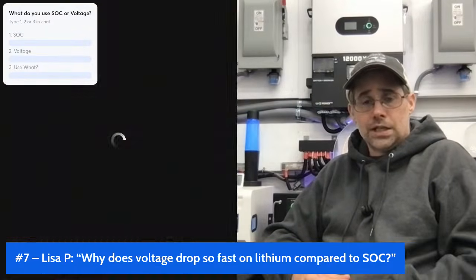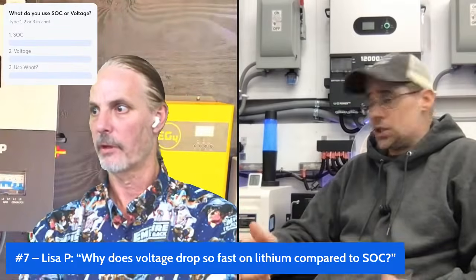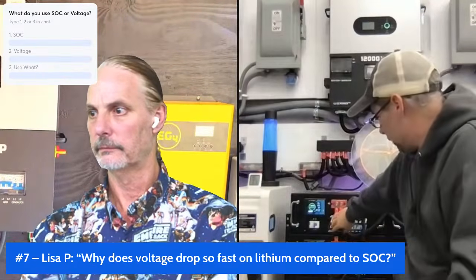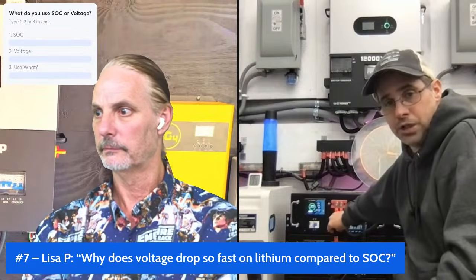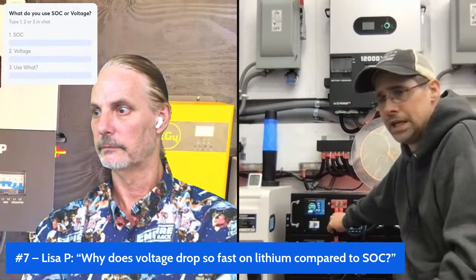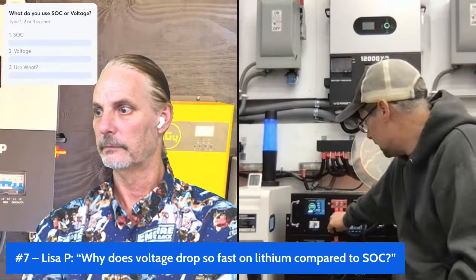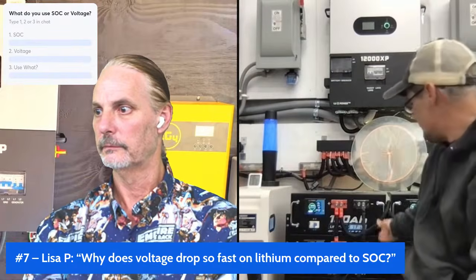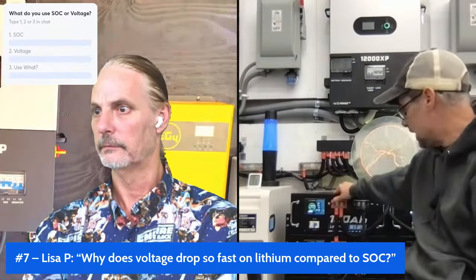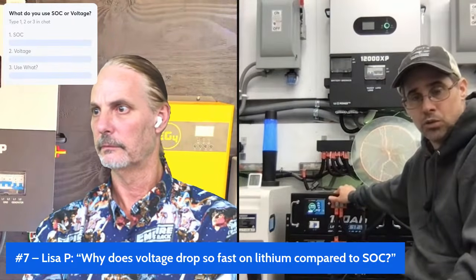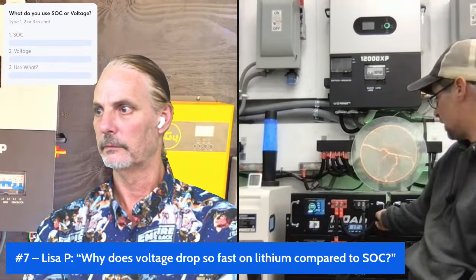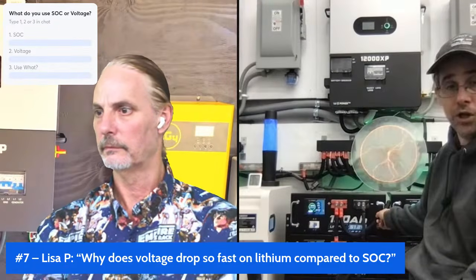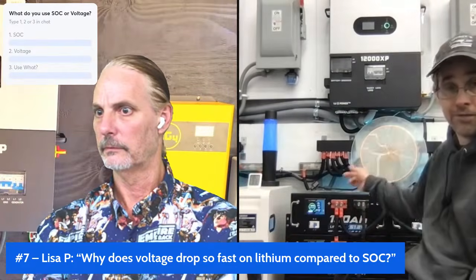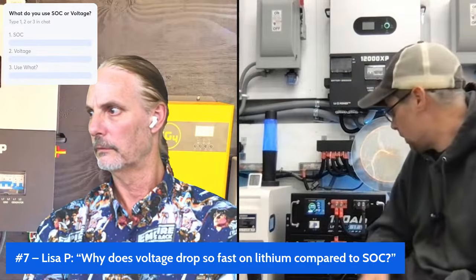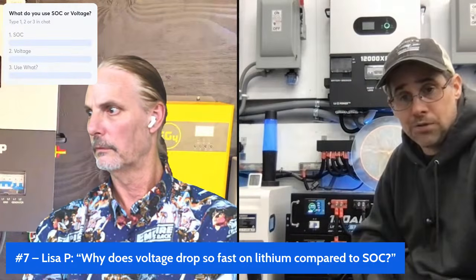Definitely overdo the wire size for the amount of amps that are going through. I've got 2/0 cable, and a lot of these batteries come with very thin cable to connect them all together. Some will use 4 gauge, 6 gauge. 2 isn't bad. But the problem is, if I take the output of these 3 batteries that are connected together, each one has a 100 amp BMS. Well, that's 300 amps that can go through this wire, and I've got 2/0, so I can flow a lot through it. And then I have it fused for that 2/0 cable. But you don't want to go with thin cables, because it's going to be very hard to keep your batteries balanced, or it's definitely going to play a role.